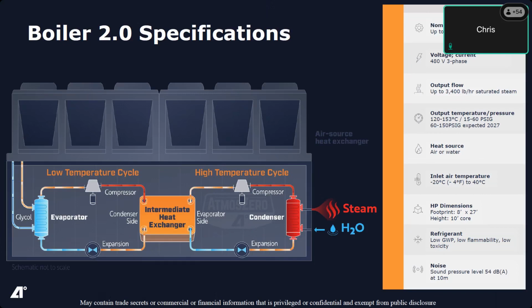Last but not least, you'll see the air coils on top. So we have a 6-cell air coil shown there. The air coils do come default with defrost capabilities, so you don't have to worry about that high humidity, very low temperature section and frosting up coils.